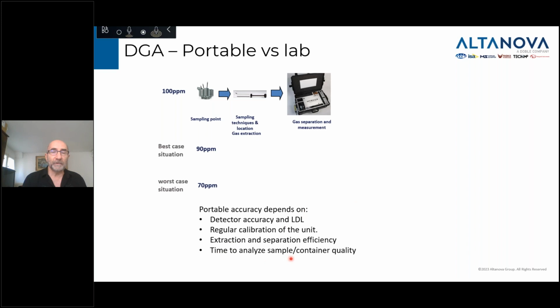And again, the time to analyze a sample and the container quality. Container quality is very important, especially if you're using a syringe. There are different types of syringe, and how tight they are at the piston is usually where you lose a lot of gas. Also, how fast do you go from the moment you take the oil in the container to transferring it to your equipment? If you do it right on the spot, you have a higher chance of not losing gases and a higher accuracy, versus putting it in a syringe and waiting 24 hours or a couple more hours because the operator is very busy. During that time, you're going to start losing gas again, especially the light gases.